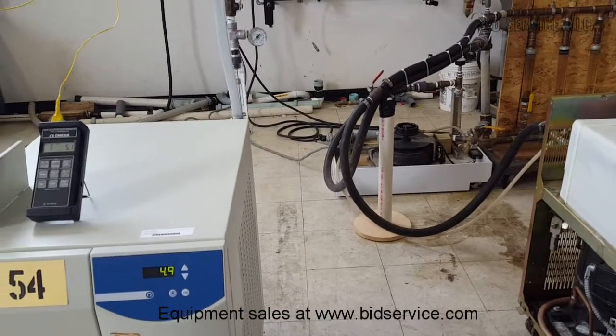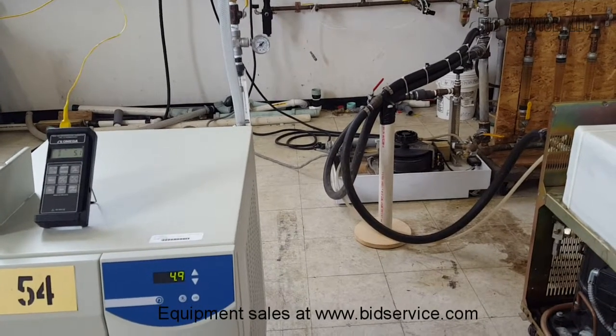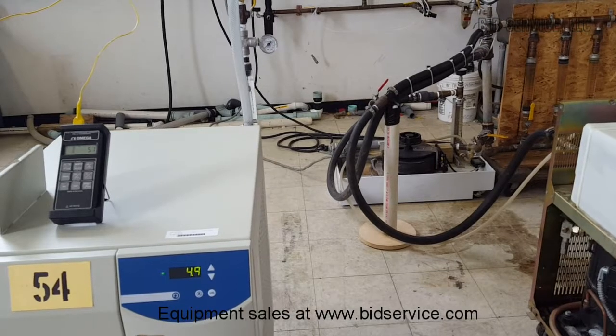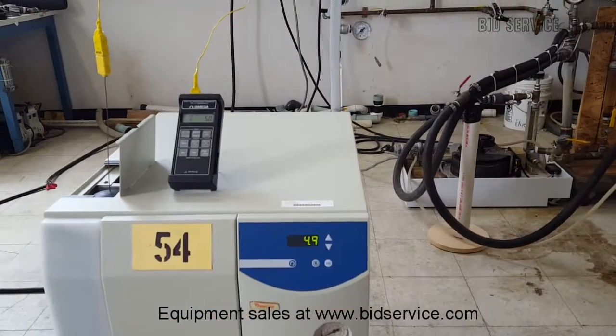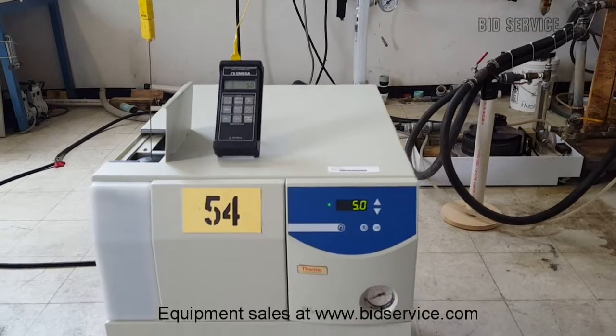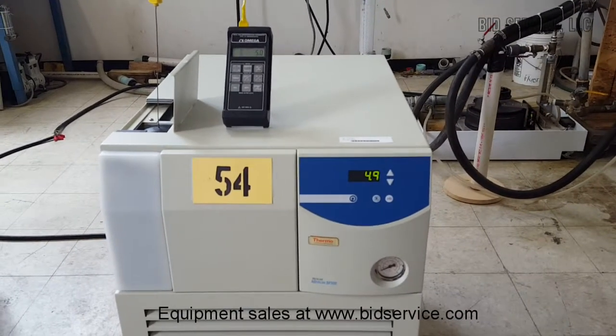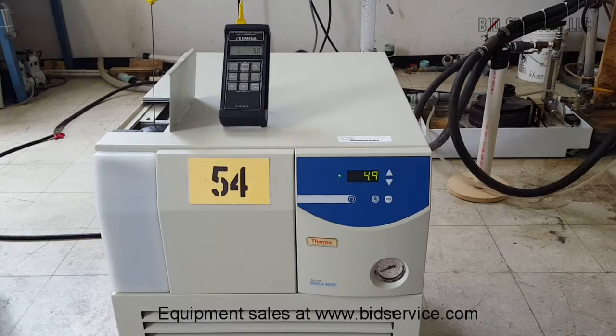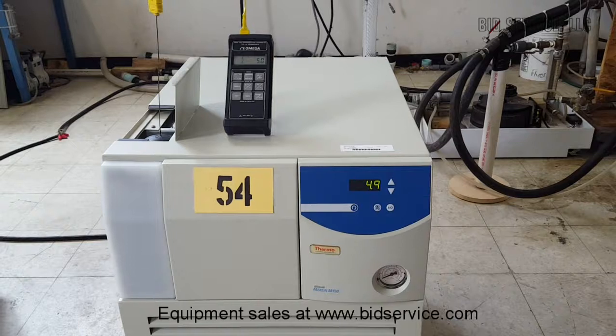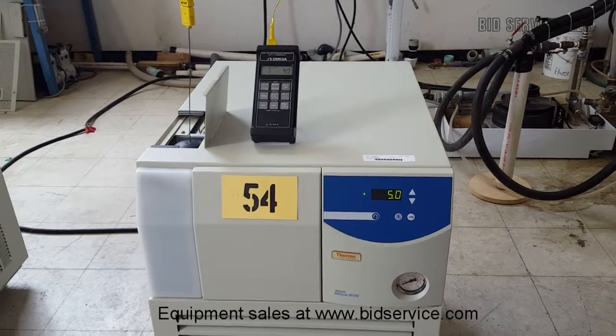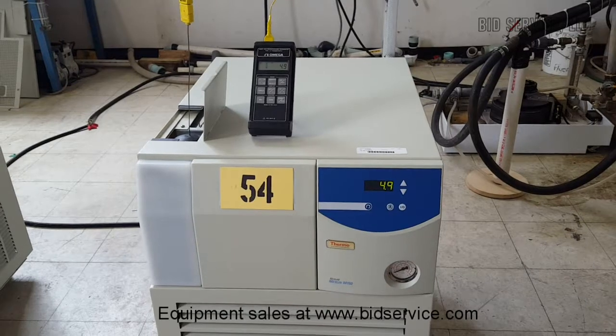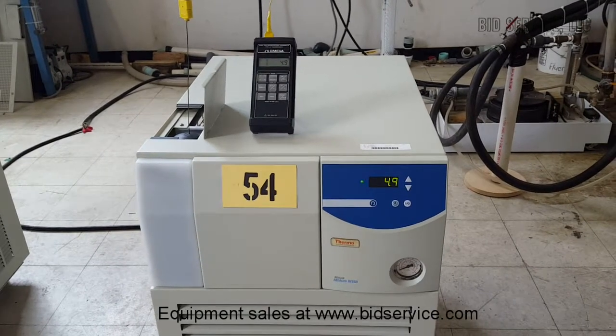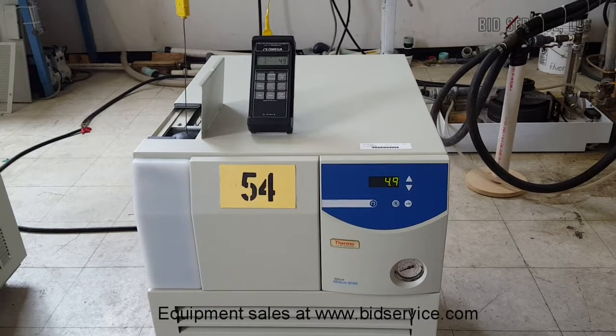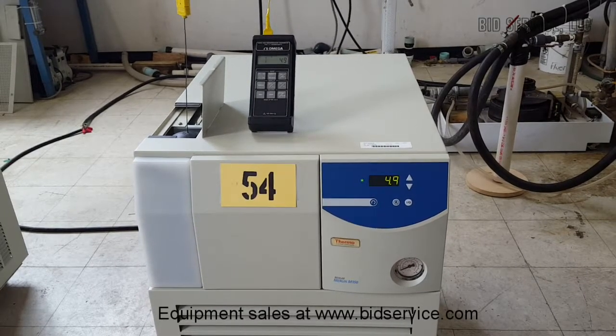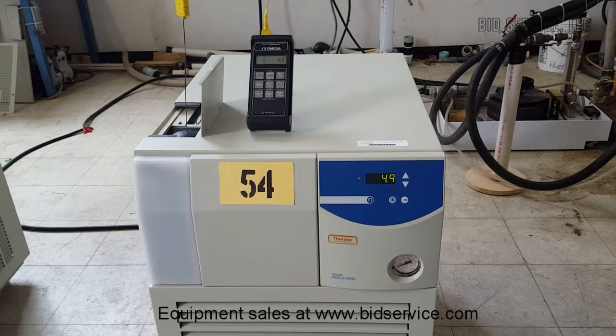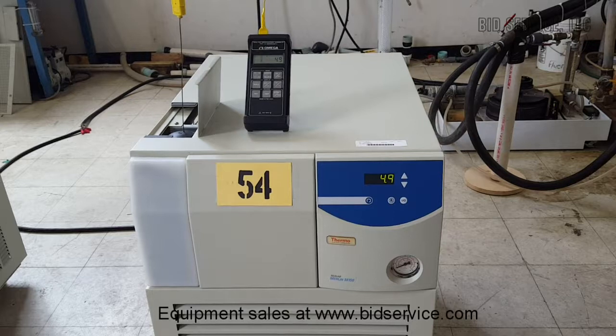We have a small one and a large one that we put together, and that's about 4.4 kW. So this was tested at about 4,400 watts, and we ran it all afternoon, and it was able to hold 20 degrees C for that entire time. The other thing that was good about this is, even though this has a smaller reservoir, all of these lines here are a large diameter. So once we had all that water hooked up, this was circulating the entire system, and it was able to hold that entire system of 4,400 watts for about 3 hours yesterday afternoon.